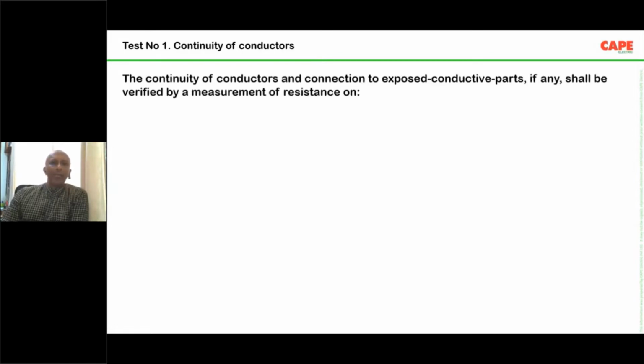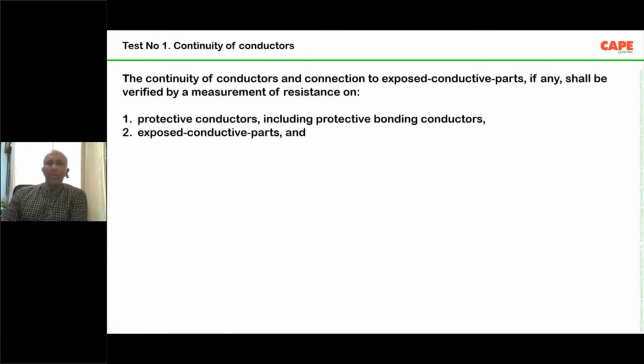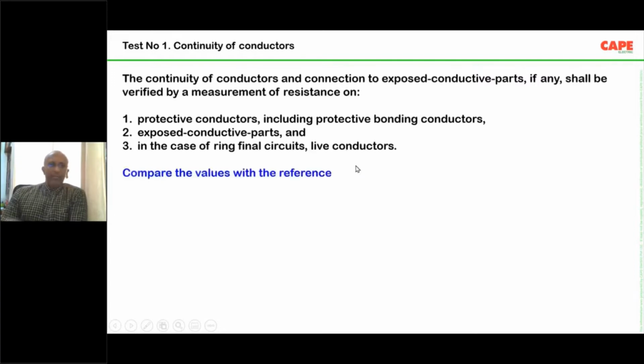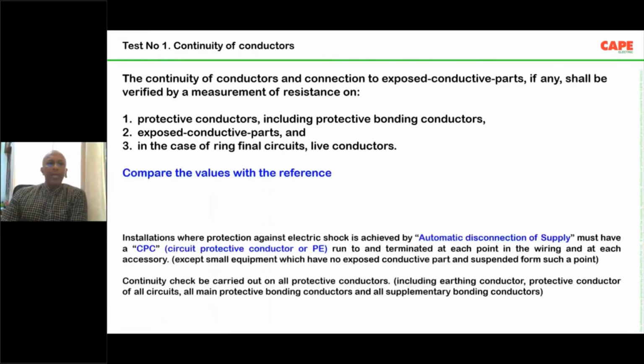It is nothing but the measurement of the resistance of a conductor which you have put inside a conduit. After installing the conductor inside the conduit, we are supposed to measure the resistance and check it against the available data. Say, for example, protective conductors, including protective bonding conductors. Basically, the first one is about the earthing conductors, the second one is also earthing conductors, and the third one is the final ring circuits, live conductors. The live conductors, meaning the phase and the neutral conductor, shall also be tested, and the values compared with the reference.